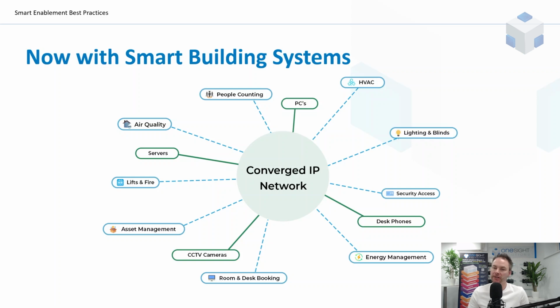So where do we come in as a system integrator with an eye on best practices? To advise on the segregation and what needs to talk to what. The IT folks might well assume that lighting devices don't need to talk to HVAC devices. But what if we know that the occupancy signals from the lighting presence detectors need to be shared directly with the fan coil units on the HVAC system? It would be negligent of us to ask for the two VLANs entirely to be able to talk to each other. Instead, if we can, we should be advising specifically what devices may need to talk to what other devices, and using what protocols.